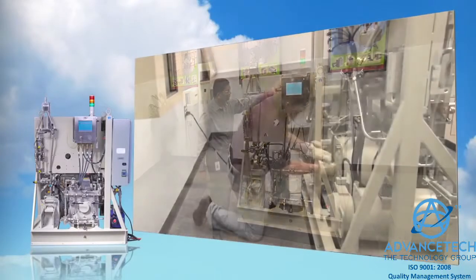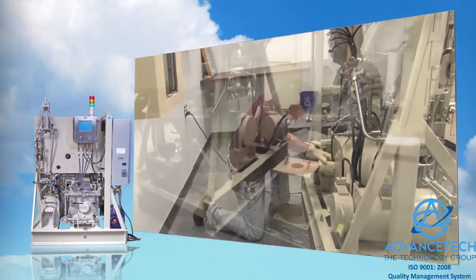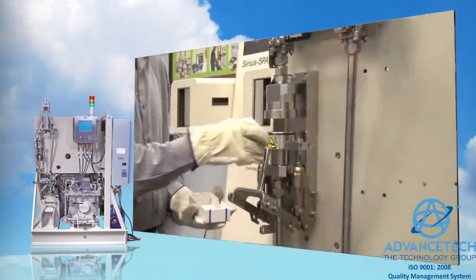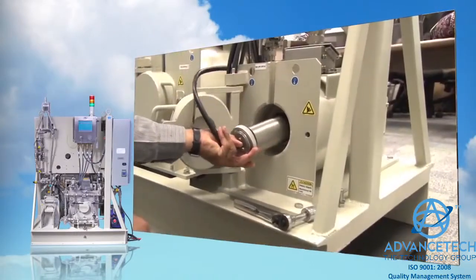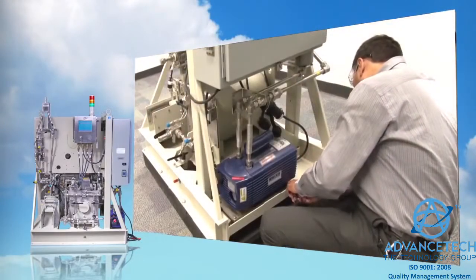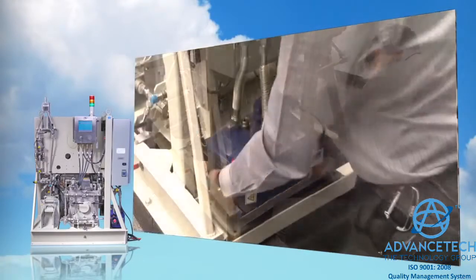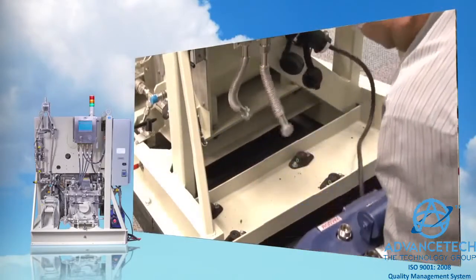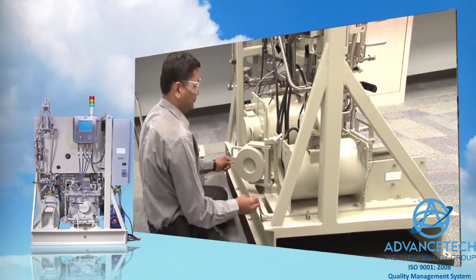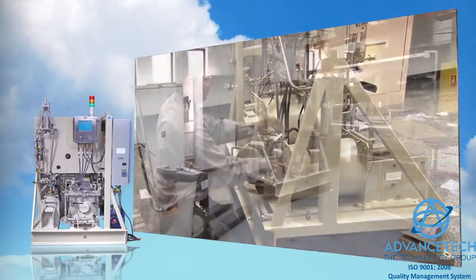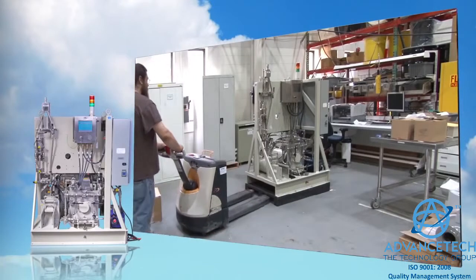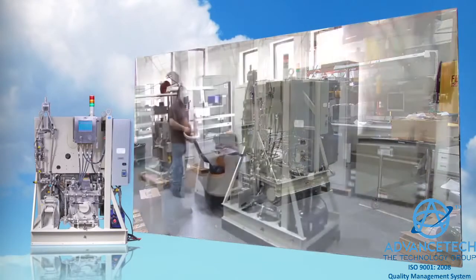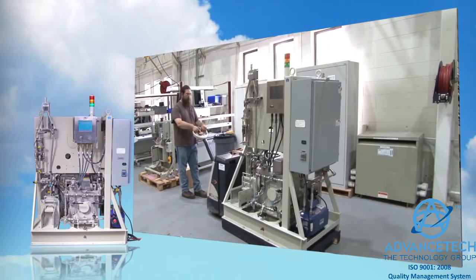The modern open frame construction of this system takes into consideration ALARA principles with its easy access to maintenance, calibration, and sampling points. A main objective of the system design was to keep component replacement time to less than 30 minutes for key maintenance items in order to reduce potential personnel exposure. We also considered customer feedback with respect to the physical and safety challenges faced when working in cramped spaces that are common to nuclear facilities. As a result, we have designed this SafePoint monitor to provide enhanced accessibility in a low-profile, space-saving footprint.